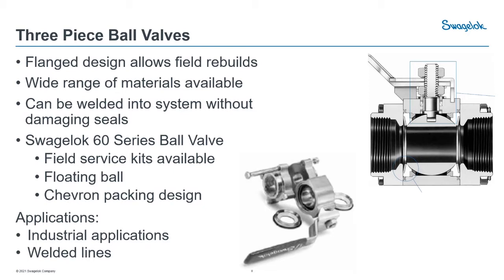From two-piece, we evolve into the three-piece ball valve — the Swagelok 60 series. It's a flange design that allows field rebuild. There are four bolts holding the flange faces together, putting compression onto the valve seats. You can loosen three of the bolts in-line with the valve isolated, swing it out, and actually remove the ball and change the seats — doing all maintenance right there in the field, in place. There's also a wide range of materials available, and you can vary the two flanges independently. Field service kits are available, making it easy to maintain.